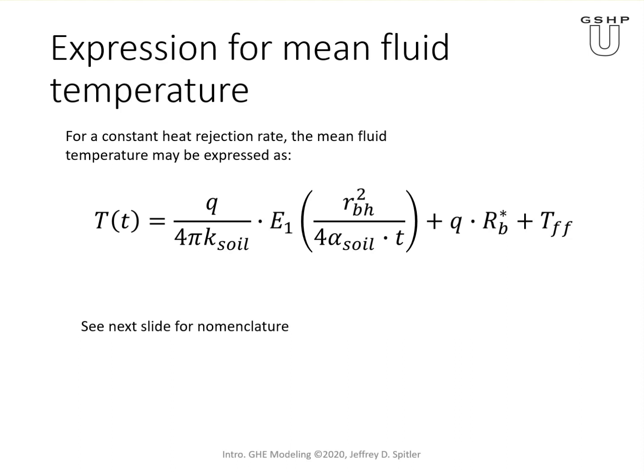If we put those together, the temperature at the borehole wall is given by this first term here — this is the temperature rise at the borehole wall. Then the temperature rise at the fluid, in addition to the rise at the borehole wall, is given by the heat transfer rate in watts per meter or BTUs per hour per foot, times the effect of borehole thermal resistance. That gives us the delta T from the borehole wall to the mean fluid temperature.